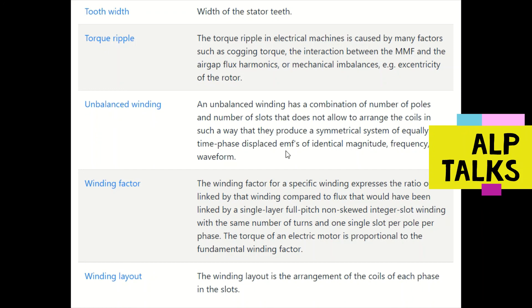Unbalanced winding has a combination of number of poles and number of slots that does not allow the coils to be arranged to produce a symmetrical system of equally time-phase displaced EMFs of identical magnitude, frequency, and waveform.